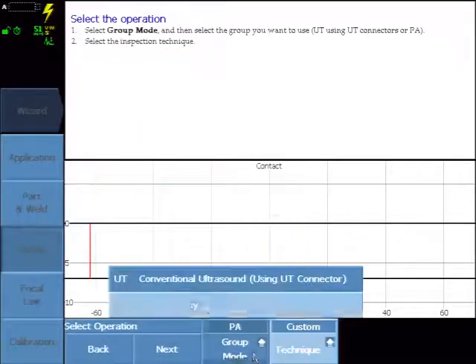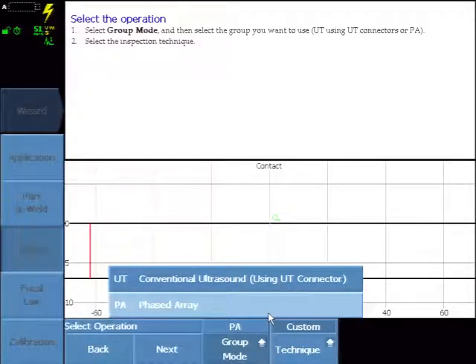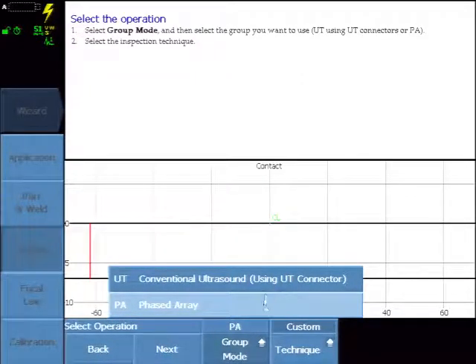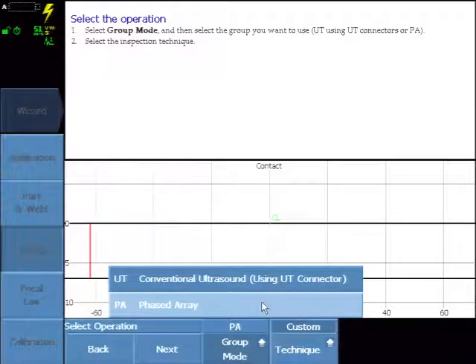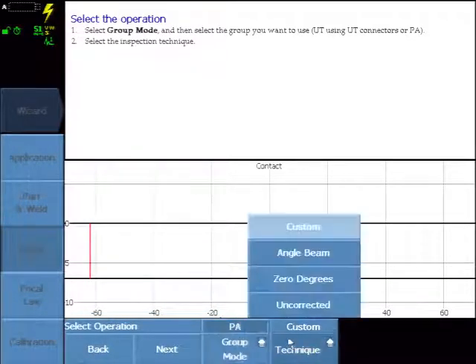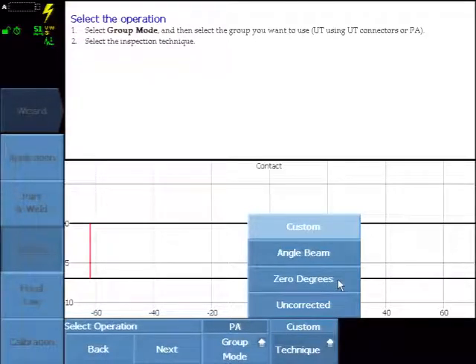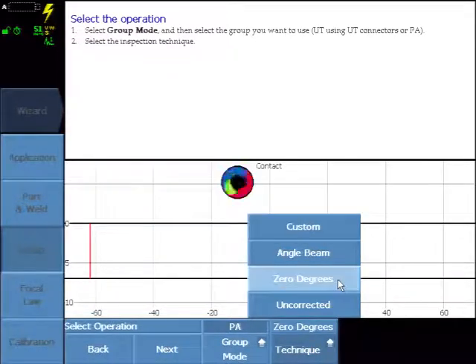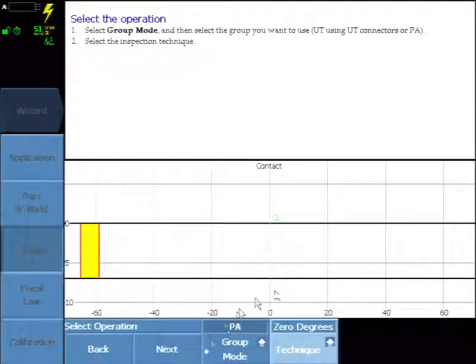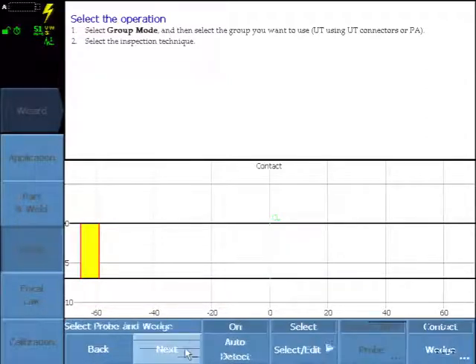Select PA Group Mode. In this case you'll see different configurations or different options here depending on the module and instrument configuration. This is a phased array inspection. And we'll use a zero degree technique to shortcut some of the setup for default zero degree parameters in the C-scan and gates.